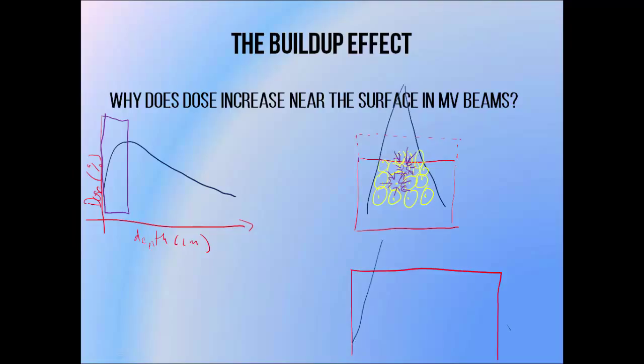Textbooks generally use a more rigorous one-dimensional explanation for the buildup effect. We look at each point as producing electrons, but only how they travel in one direction. Assuming each point produces roughly the same number of electrons, and that dose is proportional to the number of electrons passing through, different depths have a different number of electrons passing through. At a shallow depth we get 1, slightly deeper we get 2, then 3, then 4 electrons passing through. Depths with more electrons get a higher dose, so dose increases with depth — up to a point where the electron count levels out at 4.